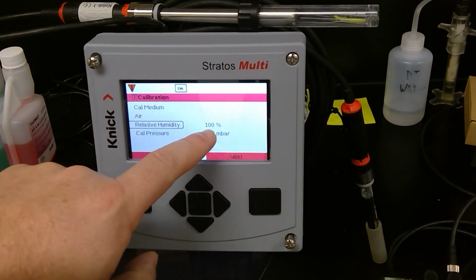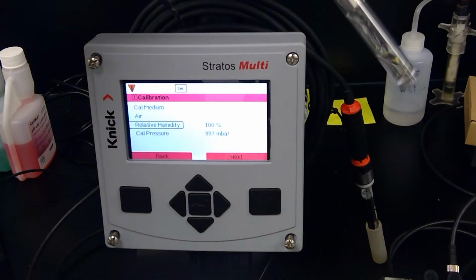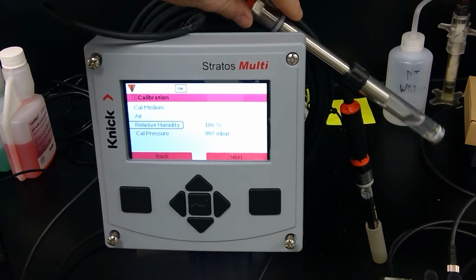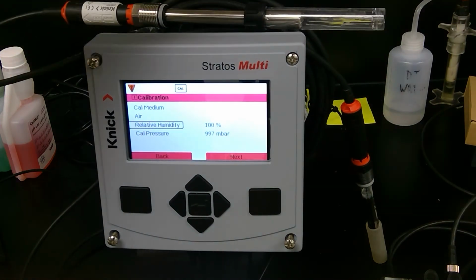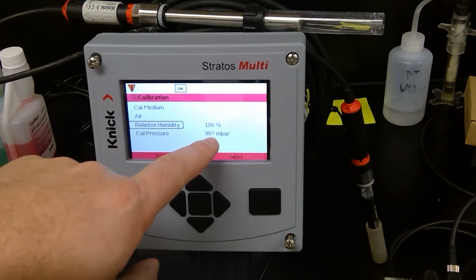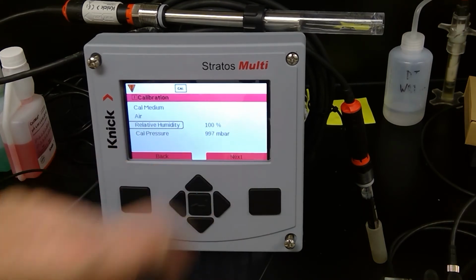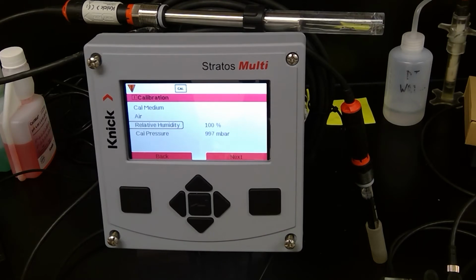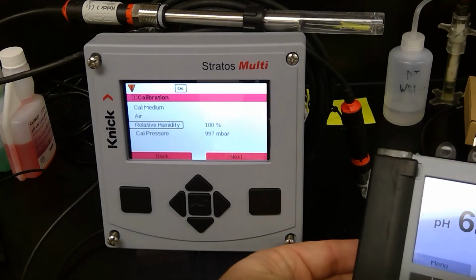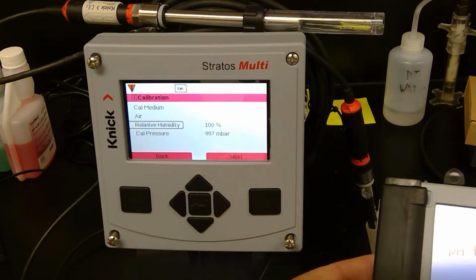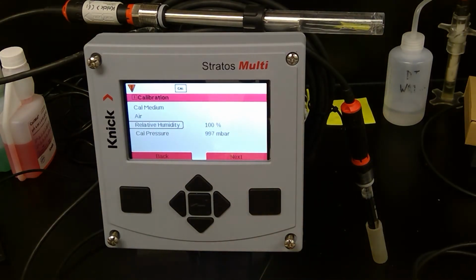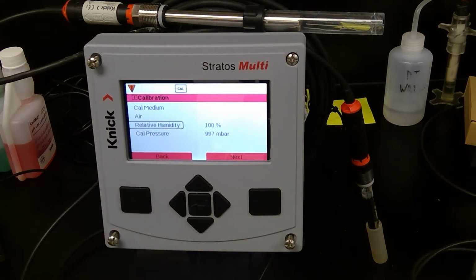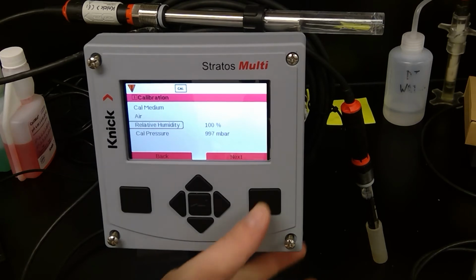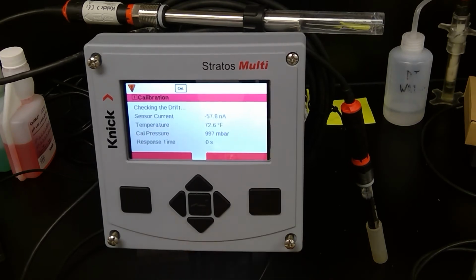As I said, I've already got it in a 100% relative humidity environment, so I want to leave it like that. So I'm going to leave it at 100%. And also I've already programmed in the calibration pressure, which is the actual air pressure here in the shop. What I did is I connected the DO probe to the Portavo, which has a pressure measurement device, and I got the measurement value off of that. You can also go onto a weather app for your location and it'll tell you what your air pressure is as well. So once you've accomplished that, you hit proceed.